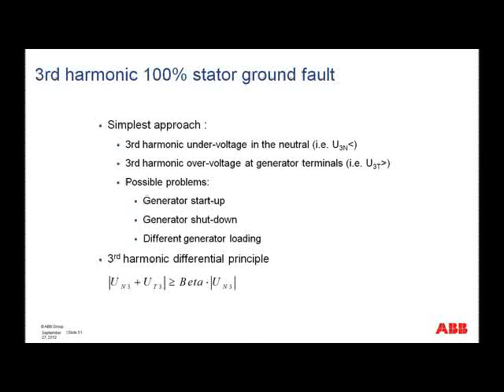Now, the simplest approach for using the third harmonic would be just to use a third harmonic under voltage for the third harmonic voltage measured in the neutral, or a third harmonic over voltage for third harmonic measured at the generator terminals. And the reason for this is because if you have the earth fault near the star point, then the third harmonic measured at the neutral side, at the star point side, would go below a threshold, or the third harmonic measured at the terminal would go above a threshold. It would increase above the threshold. But these two methods have some problems. For instance, during generator startup or generator shutdown, okay, you would need to block them.